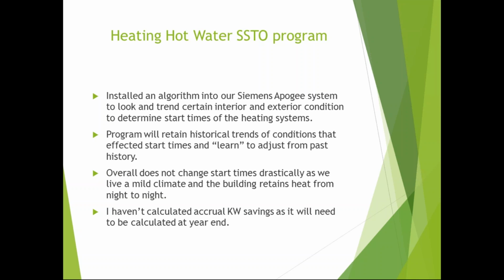High-rise buildings are 2 buildings, right? The lower is calling for heat, the upper is calling for cooling, so now I've got 2 buildings. So you take the problem area of heating that floor up, and the program will retain its trends, and then it'll learn. It'll say, hey, I started the system up at this time with the cogen system on and the backup boiler system on, and the hot water temperature was at 160, but I should have started a half hour before.